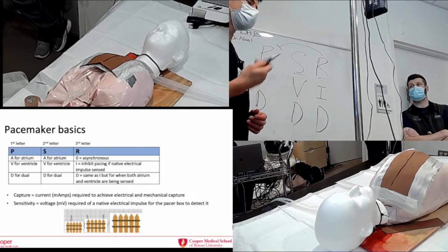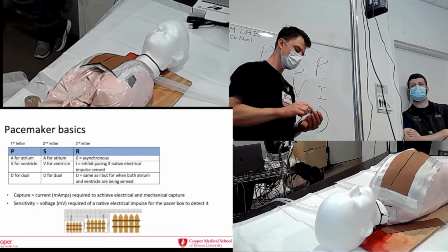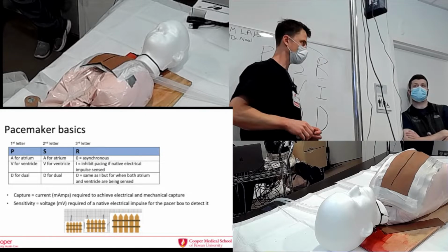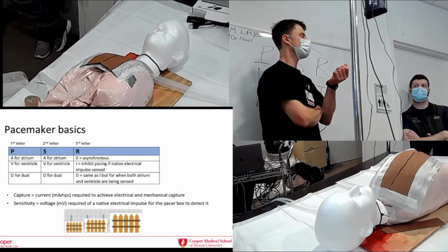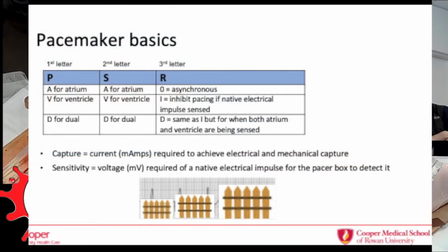So what does the sensitivity mean? So we can set, right? We can set the energy, we can set the current, we can set the milliamps. We can also set the millivolts, the sensitivity. Anybody want to give a stab at what that means? Minimum threshold required to perform the action.